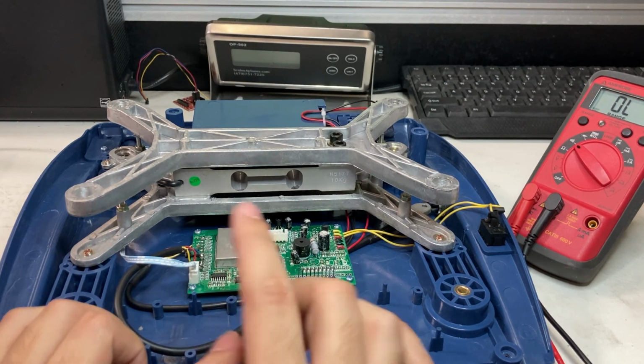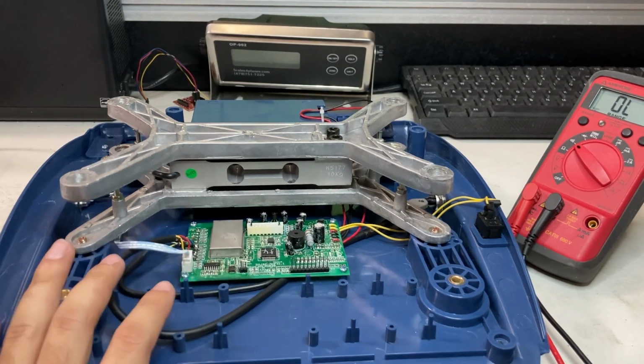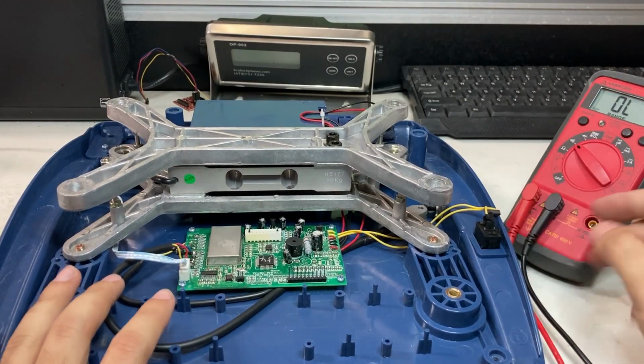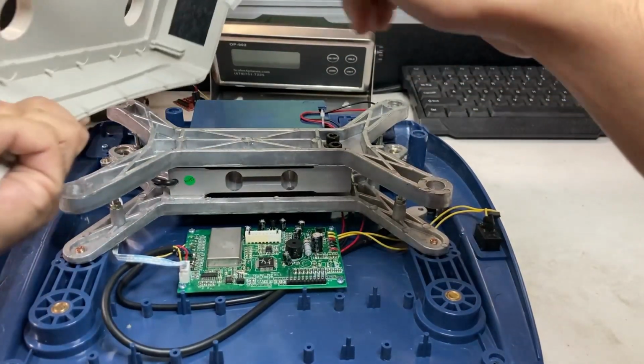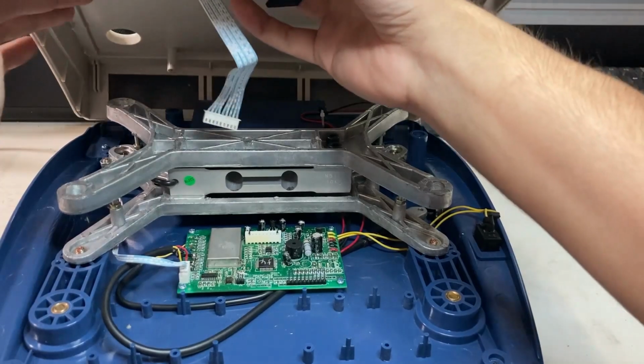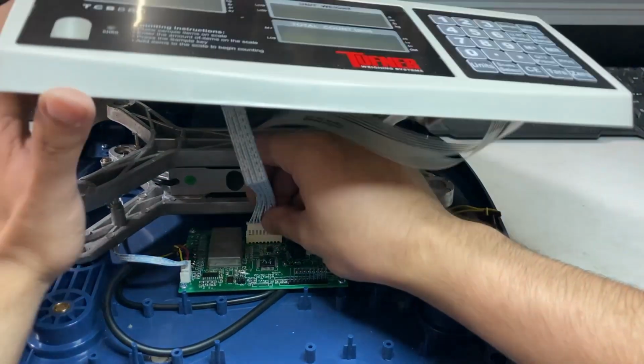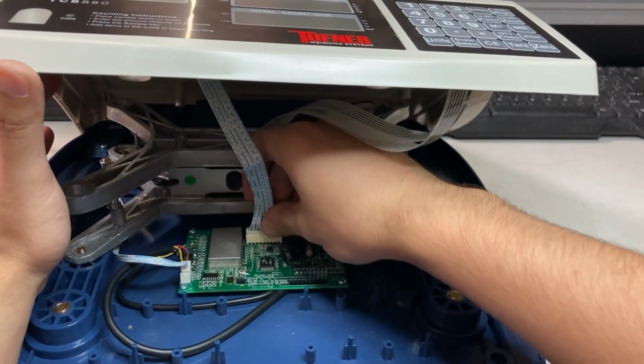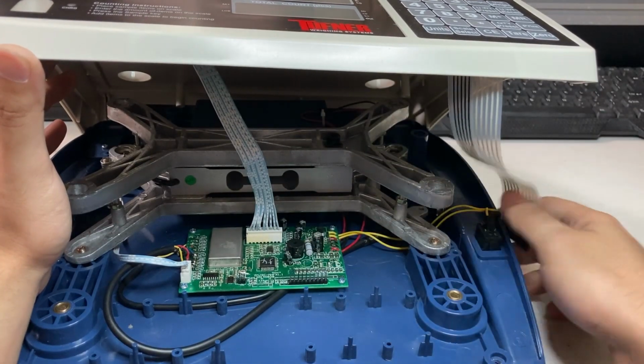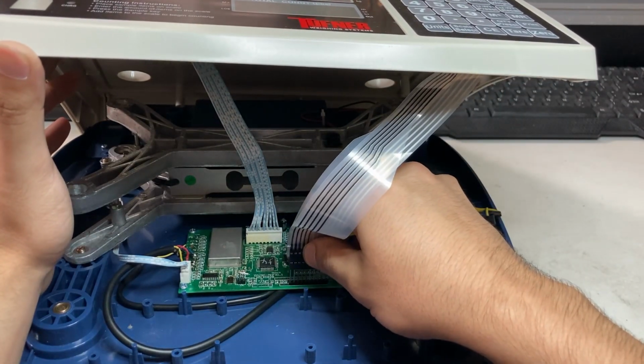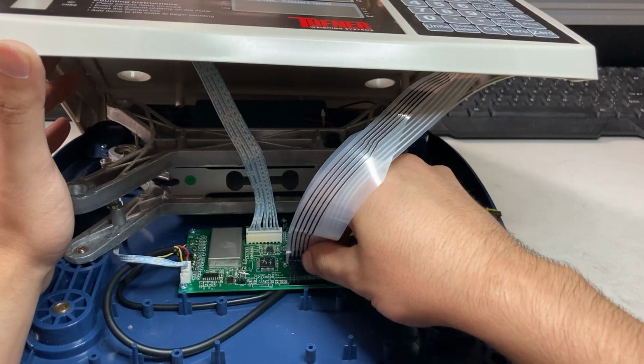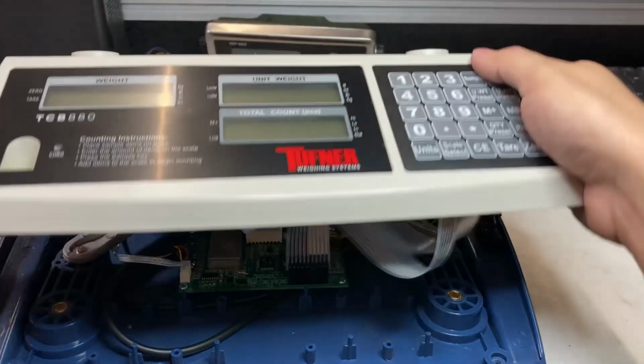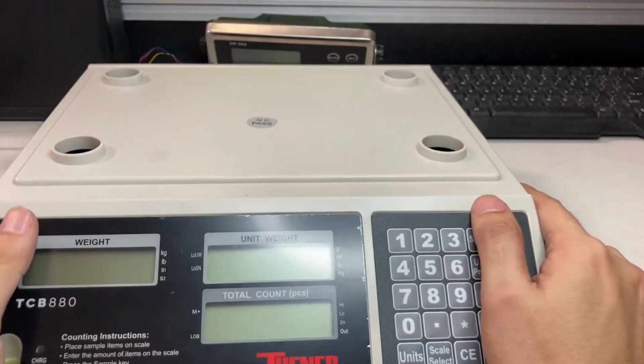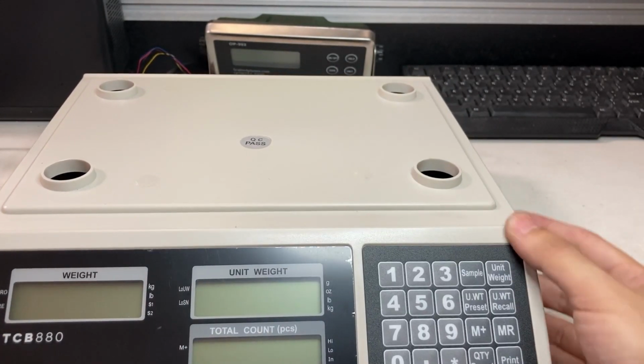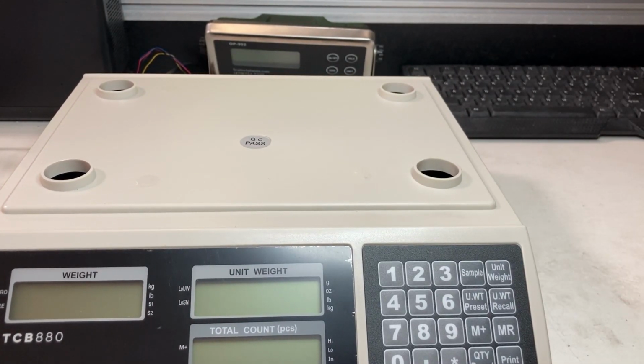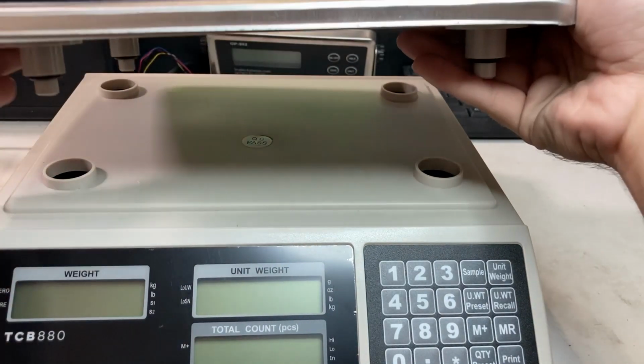Keep it on only for the next step of calibration, which is calibrating the external connection. Just don't forget to reassemble everything. Slowly put the lid back on, make sure it goes all the way in, and make sure not to bend any of those pins. And then the pan — don't forget the pan, it won't weigh properly without it.